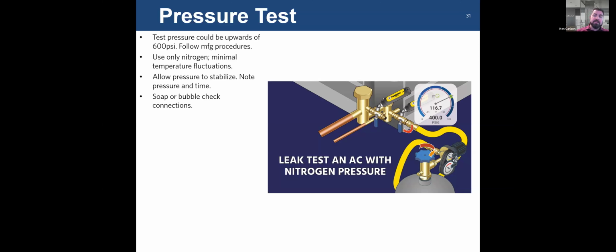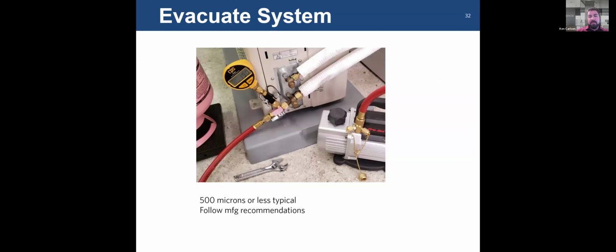All right. So once you've done your pressure test and confirmed that you've got no leaks, you need to evacuate your system. The evacuation of the system utilizes a vacuum pump. It pulls all non-condensables and all moisture out of those line sets. On your outdoor unit, and this goes for an air conditioning unit, heat pump, whatever it may be, the units all come pre-charged. These are valves right here with these hexagonal nuts. They come closed. On the unit side is all your refrigerant. On this side is your connections where your line sets are. When you pull a vacuum, these valves are closed. You're pulling a vacuum only on the line set and the interior unit, or the unit coil, I should say.